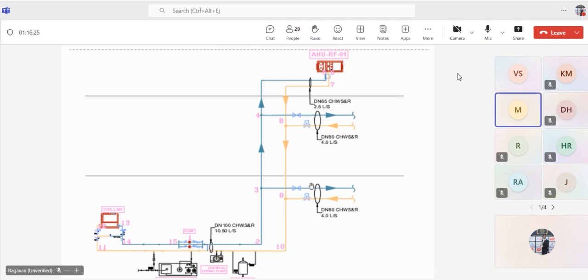And one more thing, sir. For the heat load calculation, we are not calculating the flow; we are calculating the cooling load, right? From the heat load calculation you will get the chilled water flow rate. You can calculate the air flow rate and all the remaining parameters also. We can calculate the chilled water flow also in the cooling software. But actually he's asking about the water flow rate.